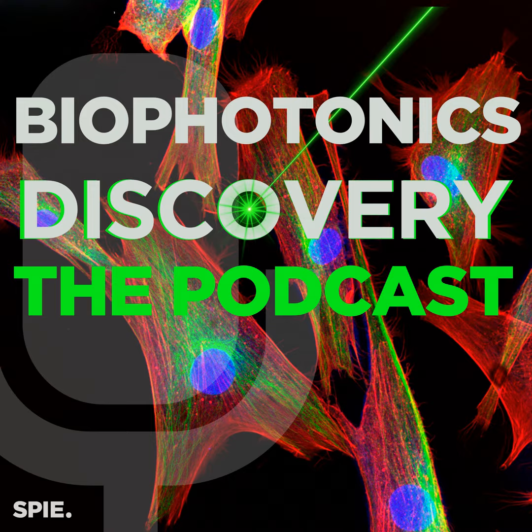And the advantage of this is that because this caustic pattern is so unique and it has so many complex features to it compared to a spot diagram, you can measure this displacement over very large movements across the sensor and get a large dynamic range for your autorefraction, meaning you can accurately measure the prescription for someone that has a high diopter of refractive error. And moving towards the imaging component of this, it's useful to compare it to conventional lens-based imaging. So with a lens-based imaging system, a point on the object is mapped to a blur on the detector, and this is your point spread function.